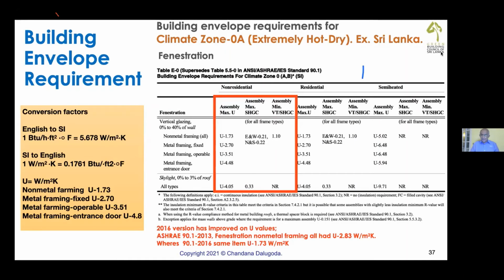Now see, this is a block wall section and this is glass. Now you can imagine how the resistance in these two structures differs. The wall is somewhat reduced, but glass flows heat quickly. The U value of normal glass is almost 6 watts per square meter Kelvin.